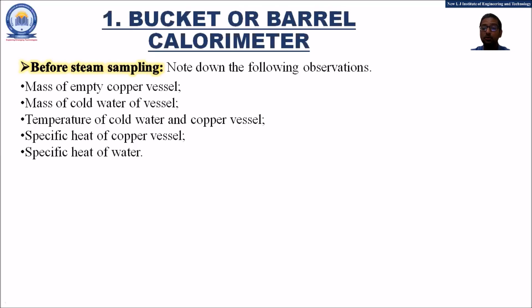Now let us understand what happens during the steam sampling. As seen in the apparatus, when we open the valve in the sampling tube, we allow the steam sample from the main steam pipe, either of the boiler, to discharge into the cold water of the vessel through the fine exit holes given at the other end of the sampling tube. The steam coming in contact with the water gets condensed because of the heat transfer, giving out its entire latent heat and a part of its sensible heat.